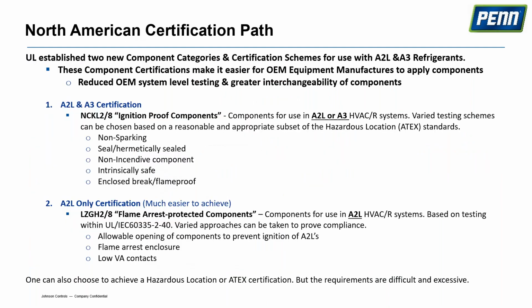Moving into the UL side of things that affects us and our controls, earlier last year UL was getting a lot of questions on compliance and certification. So they worked through this and came up with two certification schemes. The first is for both A2L and A3 certification, referred to as Nickel 2. There are various ways that you, as a component manufacturer, can get your controls certified for A2L and A3.